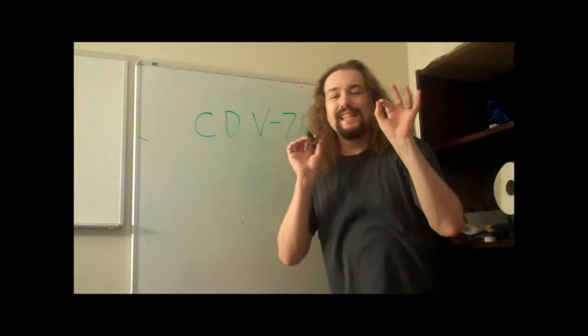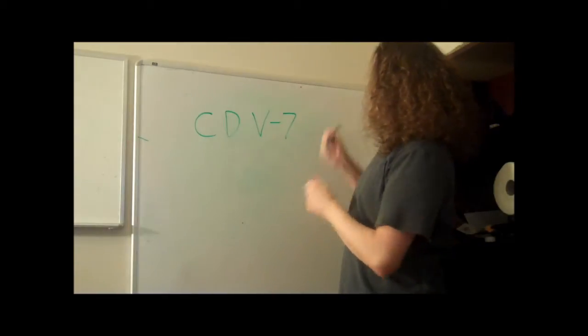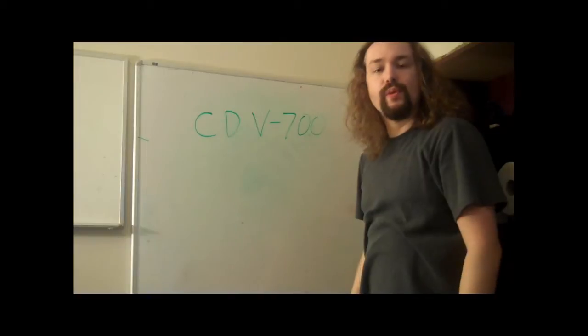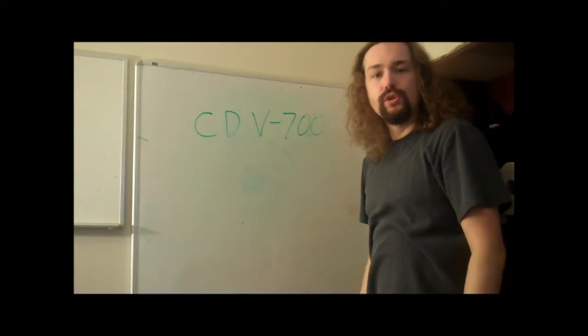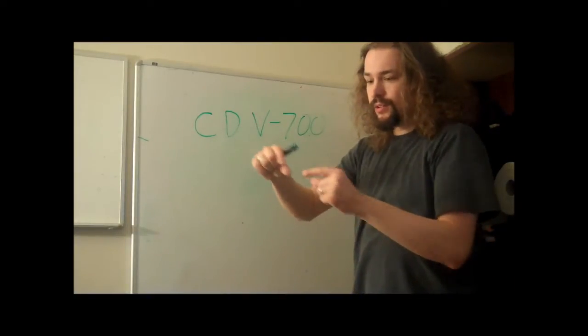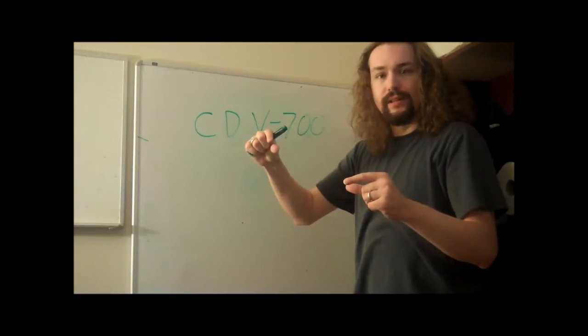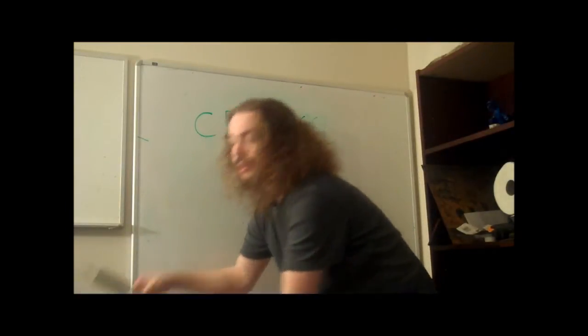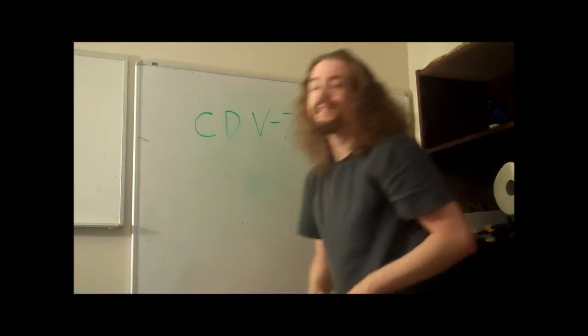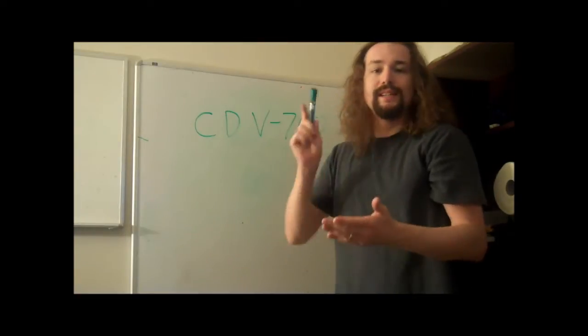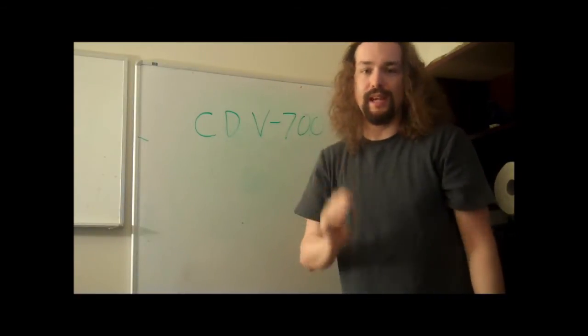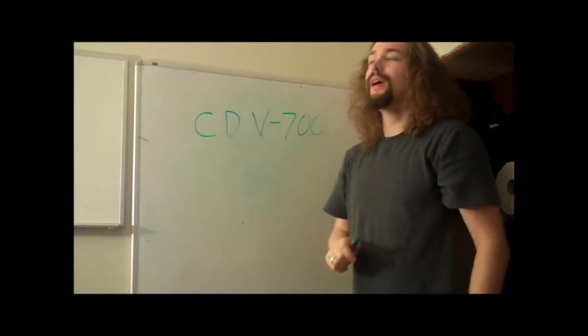The CDV 700 is a Geiger counter with a Geiger-Mueller tube. It is a little cylindrical tube that detects radiation. It's similar to the way that this unit here works, except that it has a wide pancake tube. It's the exact same technology. The CDV 700 is a Geiger counter. It can detect radiation, and it can detect low-level radiation. That's the important part, low-level.